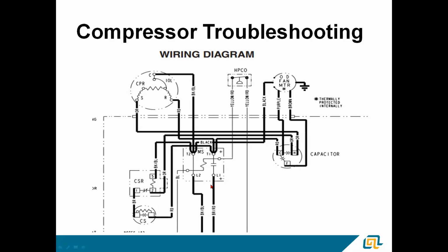Let's say you have a blown breaker or fuse on line 1. Line 2 is still hot. So you're going to see voltage to ground at line 2, voltage to ground at T2. The voltage is going to come out this wire, travel through our common wire, through our start winding. It's going to wind back up on T1. So you would measure 125 volts to ground on T1 as well. But you're reading the same side of the line. You're still reading line 2.